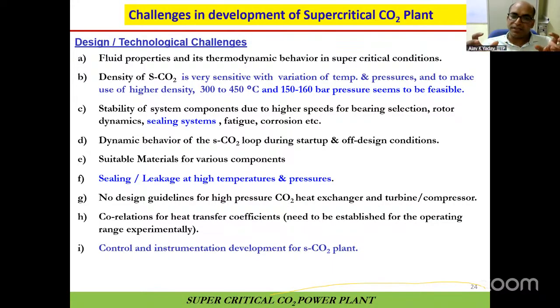Another challenge is seal design. At 1 bar or 5-8 bar, there isn't much leakage of CO2 or air, but here it's 140 bar, so seal design matters. We do have the technology though, since steam turbines operate at very high pressure, and supercritical boilers operate around 250 bar. Here we only need 150 bar, so the technology exists. Companies like BHEL or GE can develop this, and some people have already started. So sealing is an important issue.